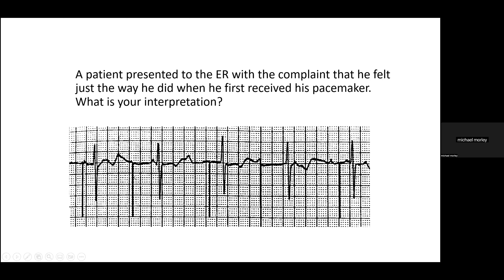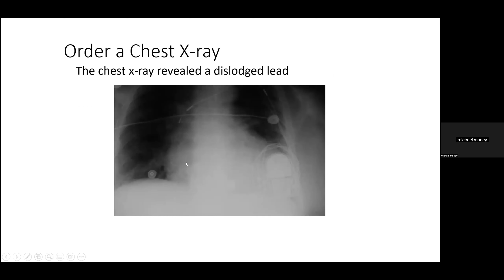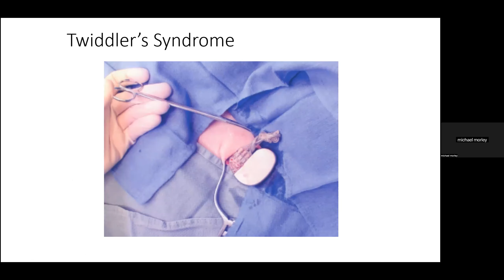And if you look at the X-ray, the reason's fairly obvious, because the tip of the ventricular lead is nowhere near the heart. It looks like the pacemaker has reeled in the lead, and this is due to Twiddler's syndrome. So some patients, fortunately rare these days, discover that they can twiddle the pacemaker around and flip it over in the pocket under the skin, and as they do so it reels in the leads and causes lead displacement.